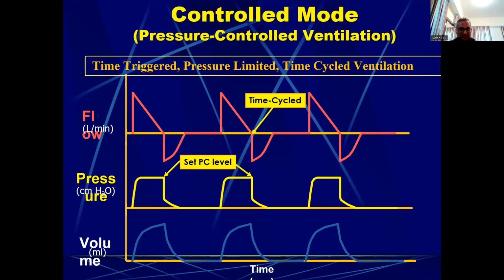But remember, this is historically the control mode. In modern ventilators, if you put on SIMV mode and paralyze the patient, he will still get breaths. You can put somebody on SIMV mode. If you paralyze them, they will still get controlled breaths, right? That is the backup. In the sense, they will get a breath. So though you may not call it a controlled breath, you may still show SIMV, but if you have paralyzed him and he's not breathing on his own, he will still get controlled breaths. Okay? Am I clear? Yes. Okay. So what are the types of breaths in this? Only controlled breaths, correct? Yes. Okay. Now we'll go to the next one.